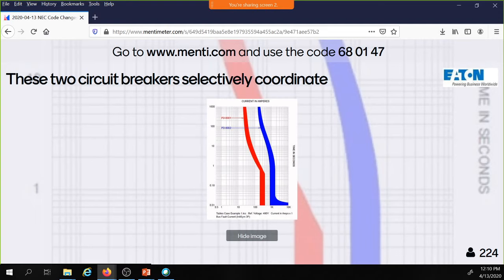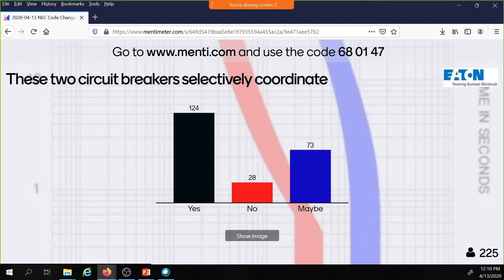In fact, based upon our testing and our selective coordination tables, I know for a fact that they will selectively coordinate up to 1,500 amps. Anything beyond 1,500 amps, and they will both open. So the right answer to this is maybe, and the reason is because I did not tell you what the fault current was that both of these devices would see. You can't determine selective coordination to any value.